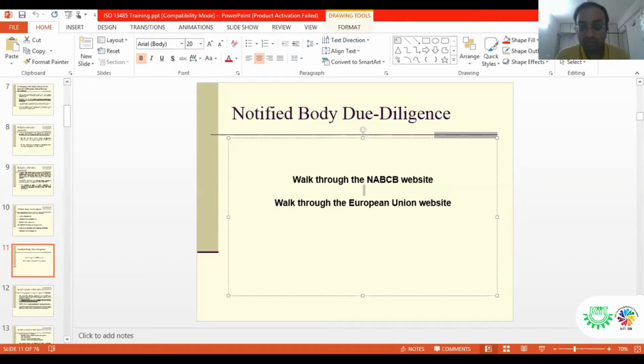Bala asked what license I should apply for manufacturing diagnostic kits. Yeah, for the medical diagnostic kits, the basic requirement is that you should have a quality management system as per the requirement of 13485. And for the manufacturing of diagnostic kits, you have to apply in MD form number 3. You have to go on the Sugam portal, and there you apply under MD form number 3. There are two options, one for medical devices and one for IVD. Accordingly you apply and upload all the documents for getting the manufacturing license for the diagnostic kits.